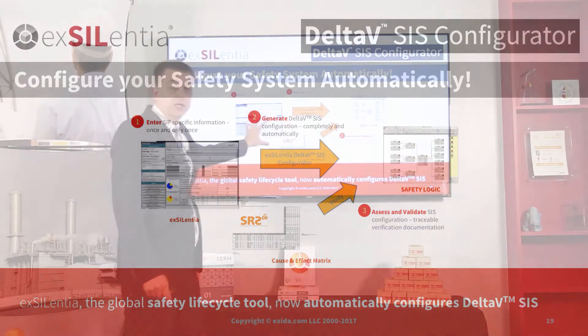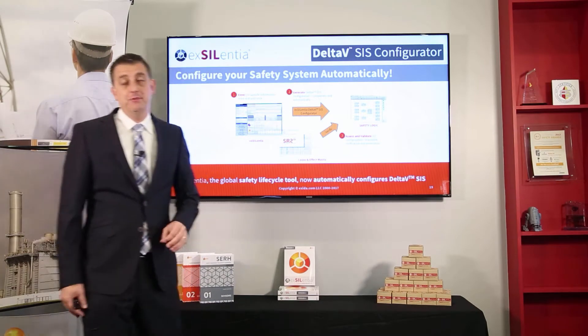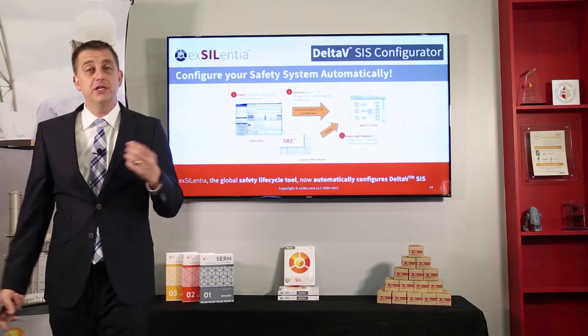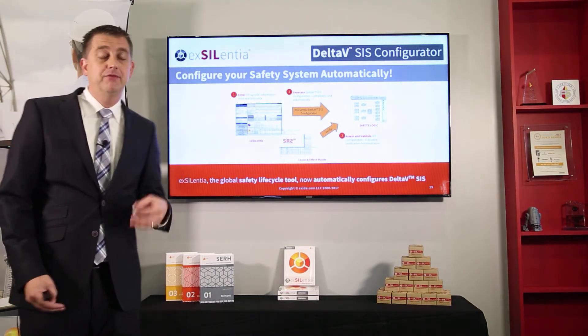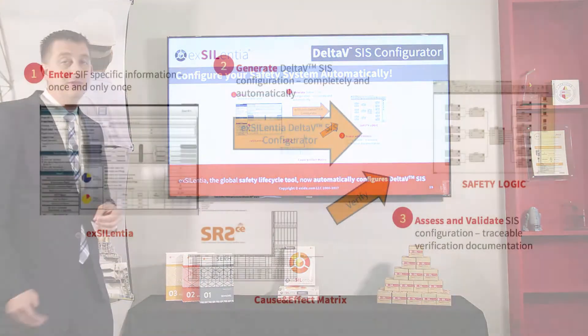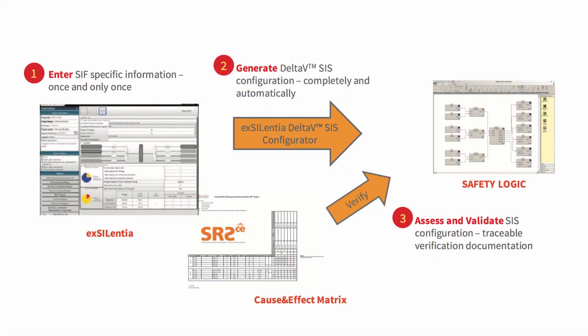In the Silver tool, you document your conceptual design. For each safety instrumented function, you document the inputs, the outputs, the voting, and so on. With that, you basically dictate what you need to program in your application program. And the utility, with a click of a button, can generate that safety logic.